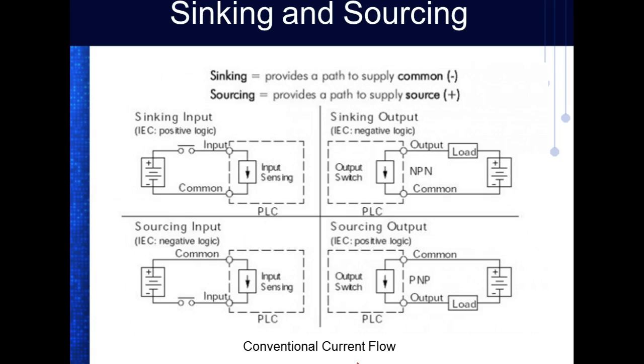So if you ever see that on the sensor, and I'll show y'all some data sheets from some of the sensors you'll be playing around with if you take the sensors class, that's where they're designated. When you look at the data sheet, sometimes it's printed on it. They're going to specify NPN or PNP. So PNP is a sourcing device. NPN is a sinking device. So we would hook that up to a sourcing PLC.